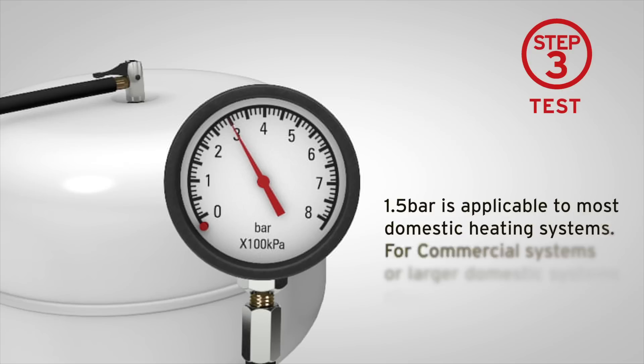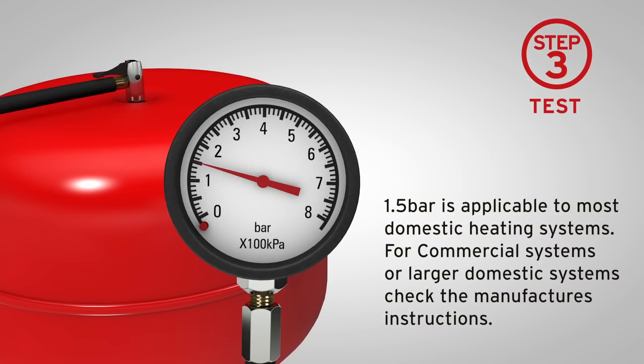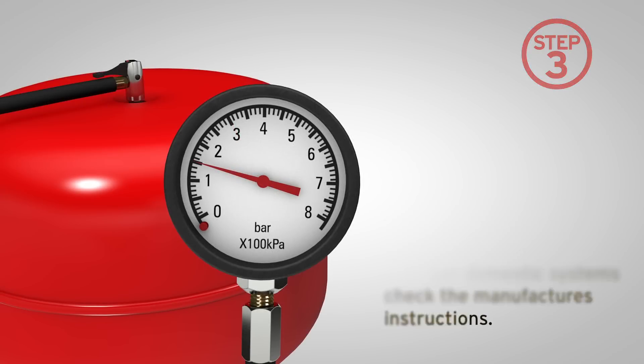It should be 3 bar for domestic hot water vessels or 1.5 bar for heating vessels. Step 4.